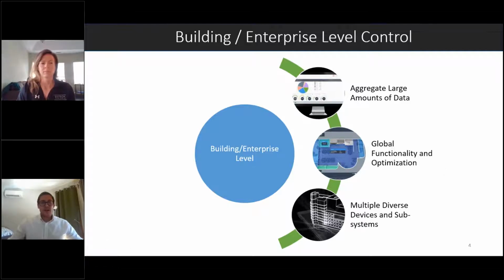Some global functionality is really a nice thing you get out of a control system. So rather than having 20 different outdoor air sensors associated with each individual piece of equipment, you could globally network that across the BAS system and make it so that outdoor air temp and humidity are pushed across to other controllers, even though it's not directly wired to them. That helps with your cost savings and setup for your system.